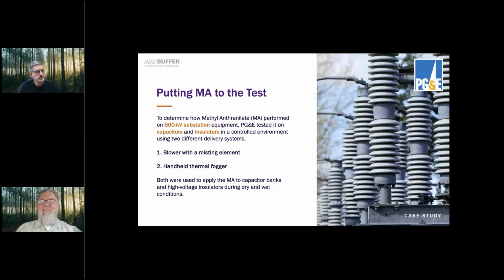So to determine how methyl anthranilate performed on 500 kilovolt substation equipment, they tested it on capacitors and insulators in a controlled environment using two different delivery systems: one blower with a misting element, and a handheld thermal fogger. The blower with the misting element is a dry vapor solution that comes out of, say, a bird buffer machine. The handheld thermal fogger we're all familiar with.